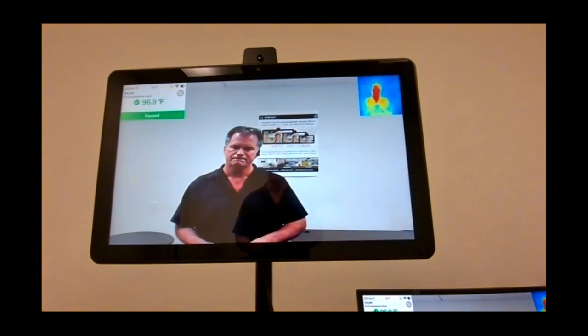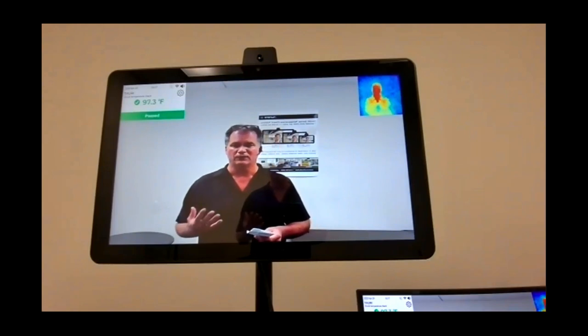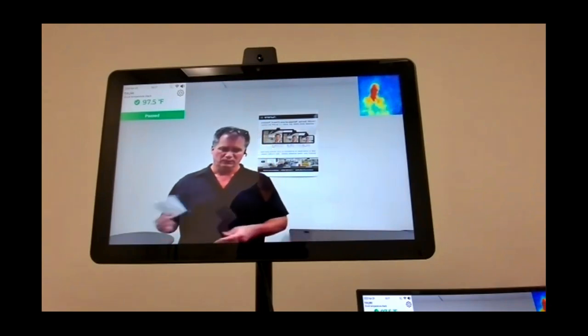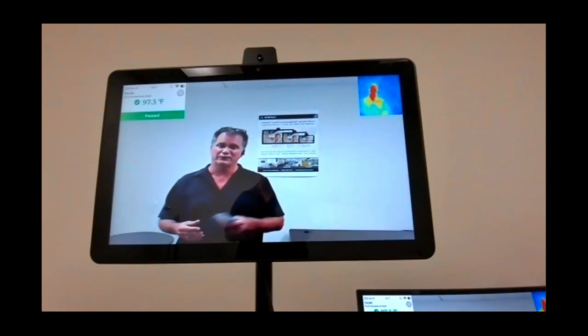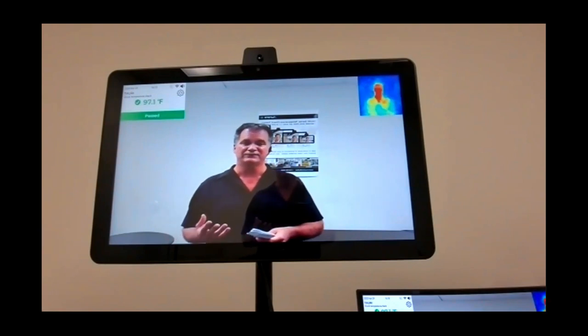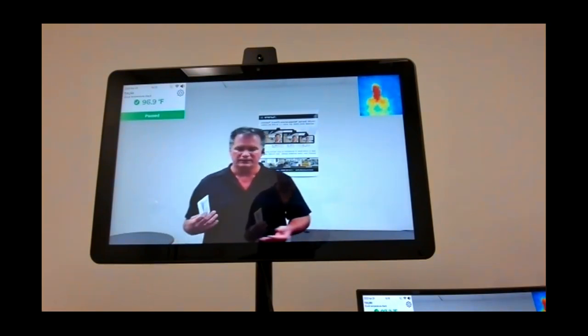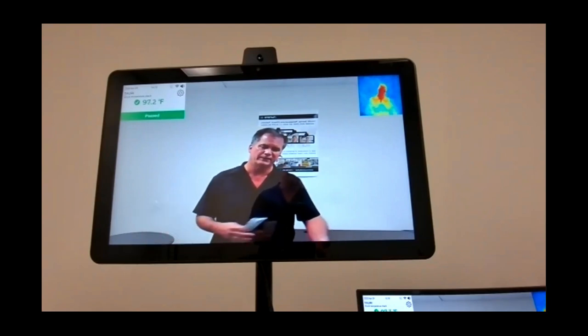Question: how well does the device handle multiple targets — people being in the frame at the same time? Currently, if two personnel are in the target area and one has an over-temp, you'll get an over-temp alert for that zone. You'd have to ask them to separate and do secondary measurements. It won't distinguish which individual triggered it, though reading the infrared display — the tones indicate where the hot spot is. Ideally people go through one at a time, but if you get an alert you mitigate it by separating them and having them walk through individually.